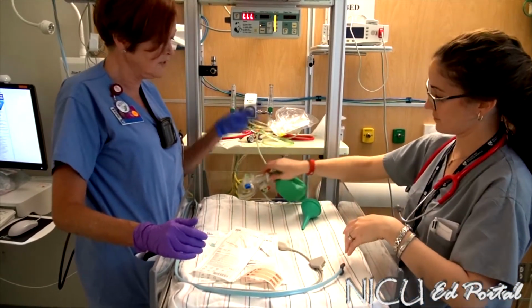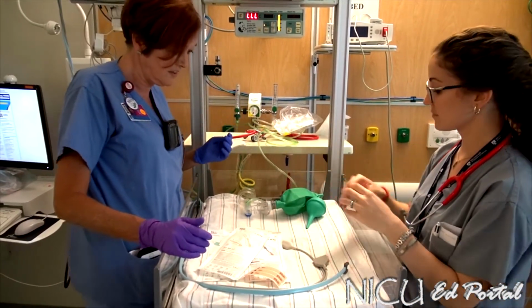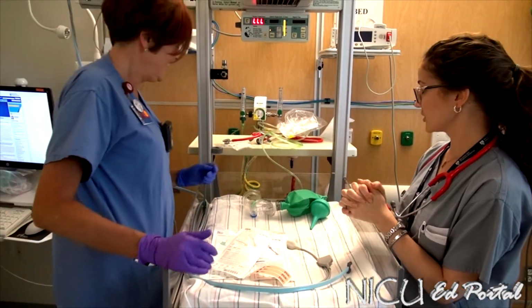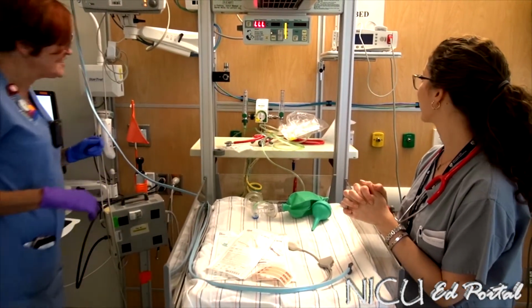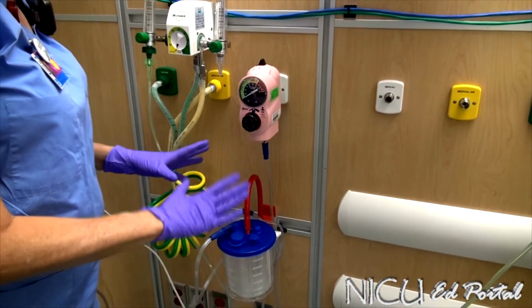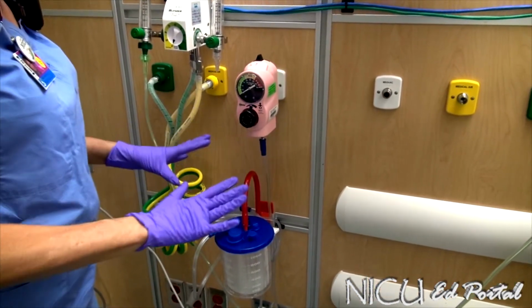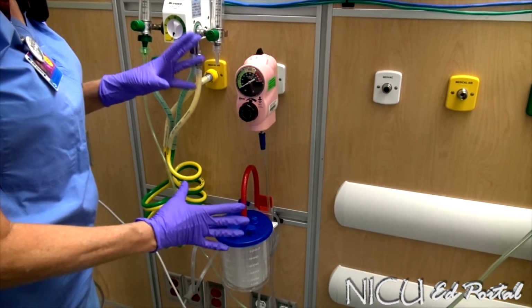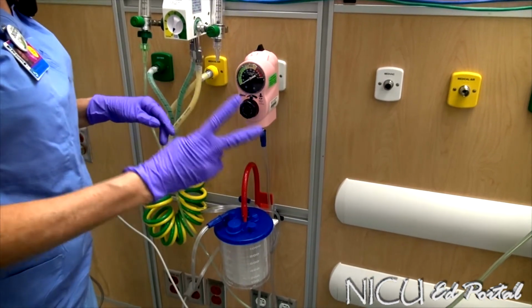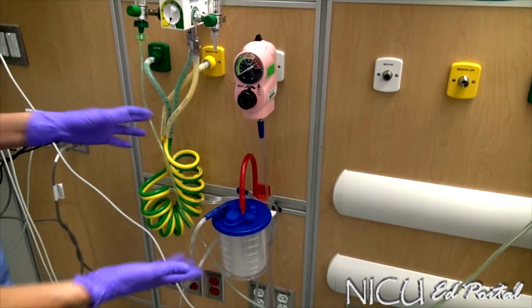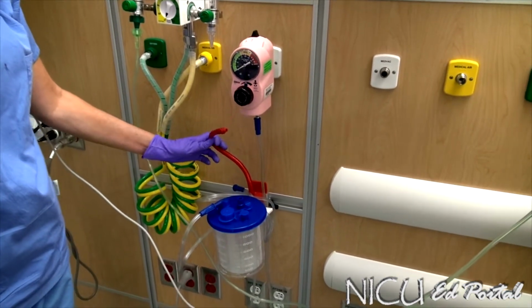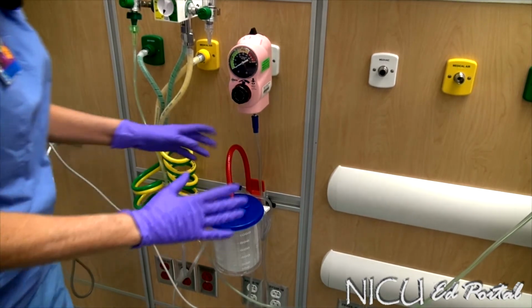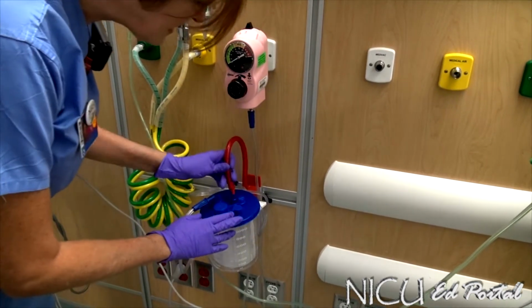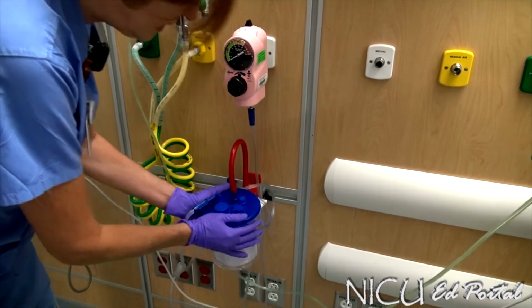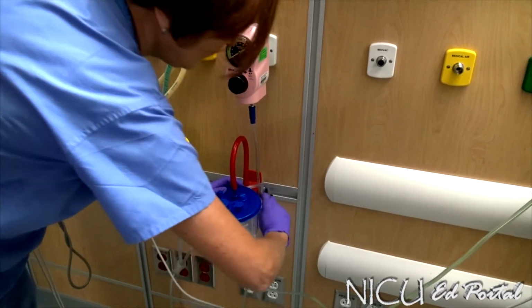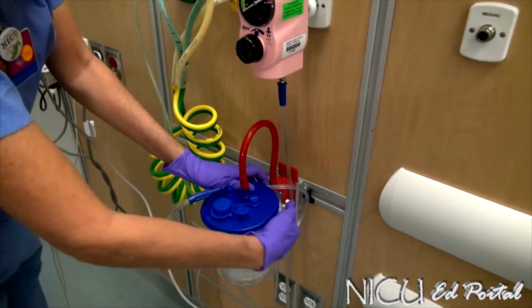So we've got 1, 2, and the third thing. What do you think the third thing is? Suction? Exactly. So suction is your third thing. You really need to make sure that your suction is all set up and ready to go. There's 2 pieces to the system, so there's 2 pieces that you need to turn on. I'm looking at this setup right now and I can identify straight away we're not going to have a good vacuum on this. So first thing I do is I make sure that everything is sealed properly on here. I turn on at the wall right here. There's an on-off switch at the back.